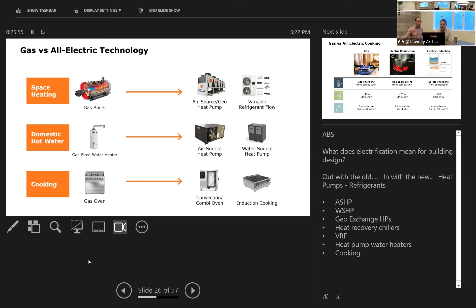For the replacements for gas boilers, on a lot of projects we're using air source heat pumps, which are similar to air cooled chillers but can operate in reverse, so they can generate both heating and cooling. We look at geothermal heat pumps as well, and on some projects VRF. All of those are all electric heating and cooling solutions. For gas water heaters, again, we'll use air source or water source heat pumps, and there is a new technology, CO2 heat pumps. The CO2 is actually used as the refrigerant in these machines. So that's another technology that we've been using.